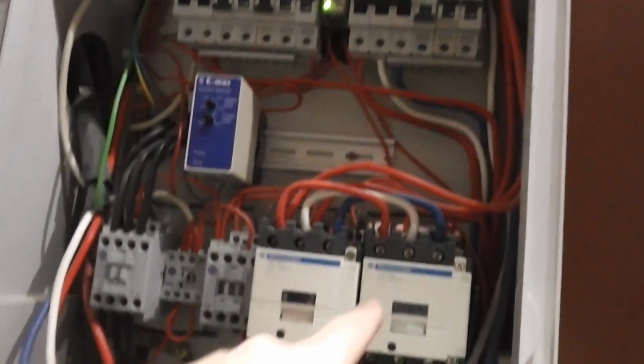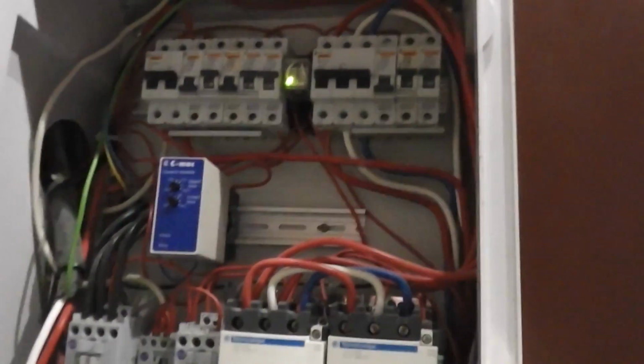What we'll see is that there's now a light on this relay. That relay is what the generator uses to switch between these two contactors - that one's the mains from the street, that one's the generator. So that one is now on, and the whole house is disconnected from the mains. That includes the server room, the whole house - all of it is now running off that generator. If there was no power from the street, it wouldn't make any difference, everything would still be running.